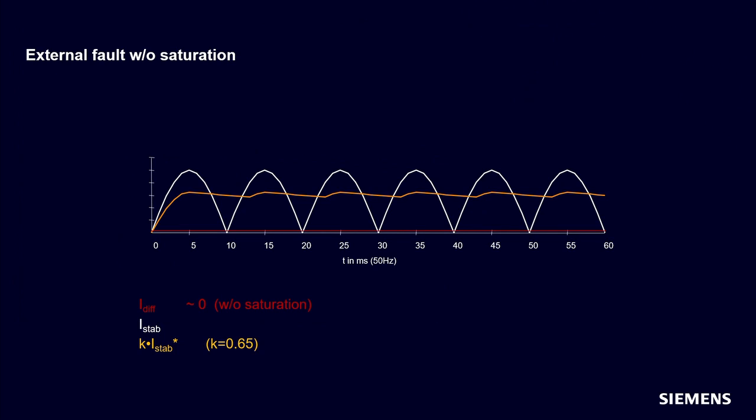And we see the calculated stabilization factor, which is going to 0. And very important, only just to once again show you on diagrams, on figures, what I have tried to explain to you. You see the modified stabilization current multiplied with the stabilization factor. That's this brown color here.